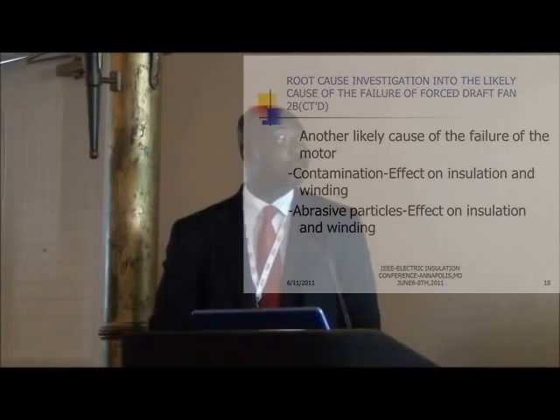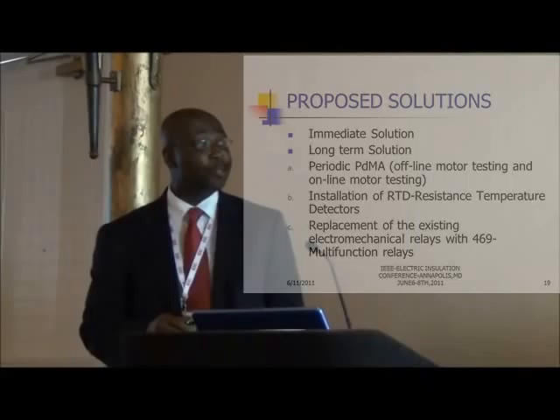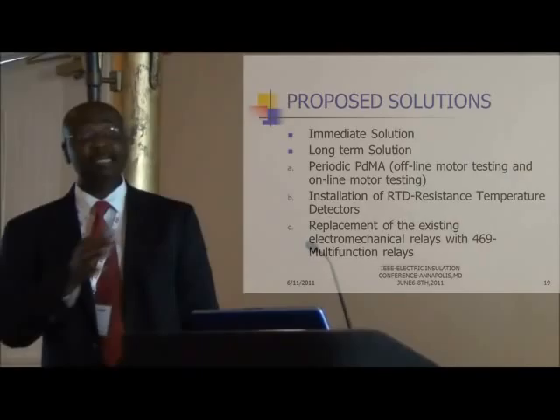The immediate solution was to remove the motor and send it to IEW, a motor shop in Illinois. For a long-term solution, we implemented a periodic PDMA testing program — similar to Baker testing — covering both offline and online motor testing. By performing online pre-outage testing, we gathered motor signatures to identify problematic motors before the outage, then performed detailed offline testing during the outage.